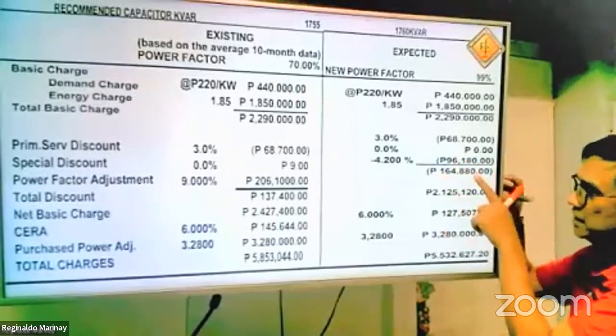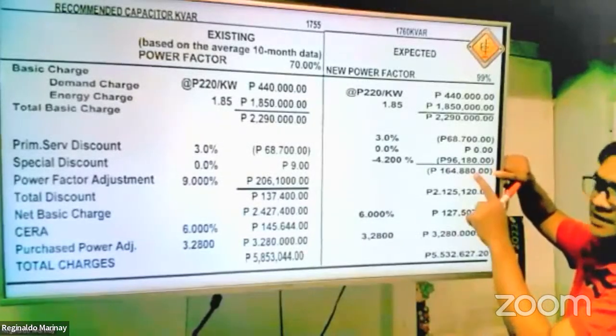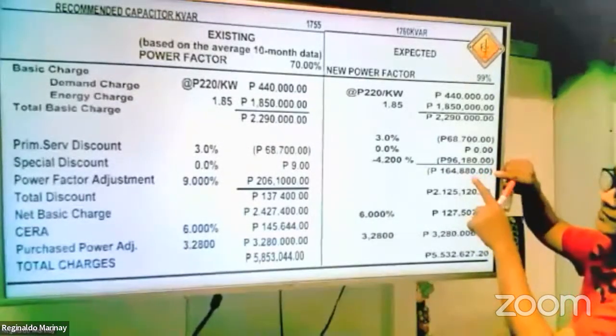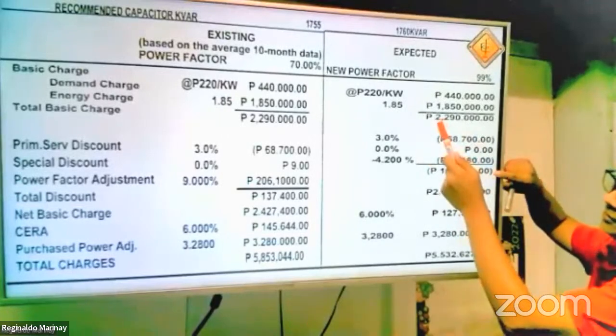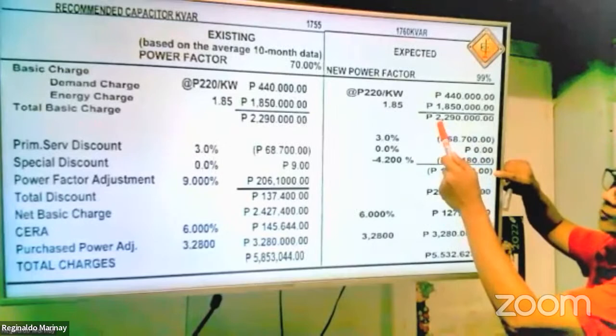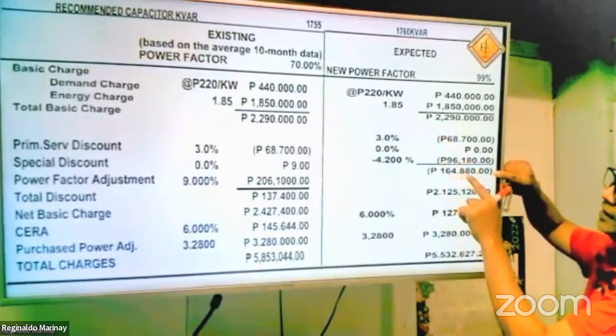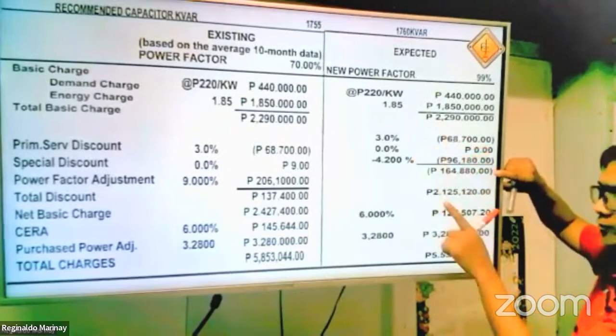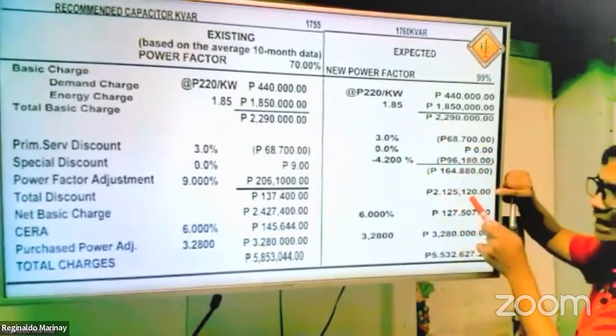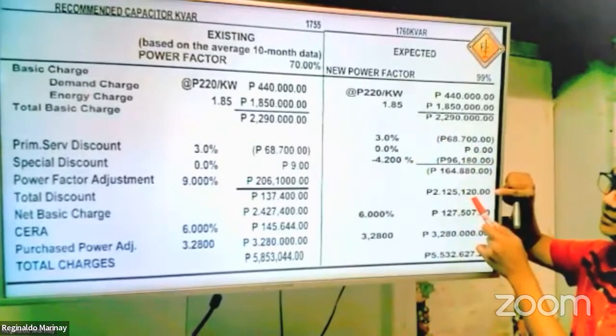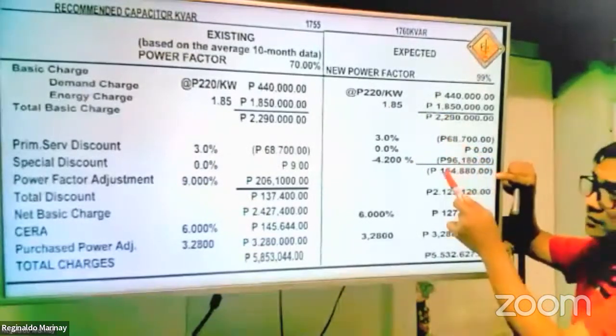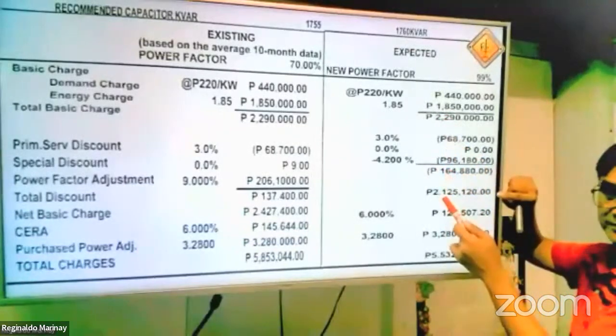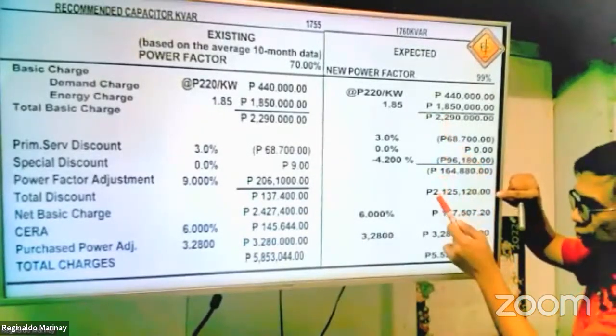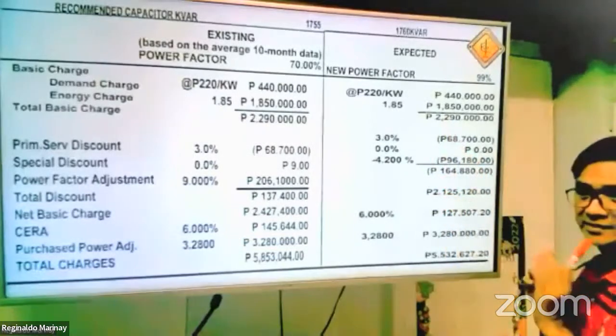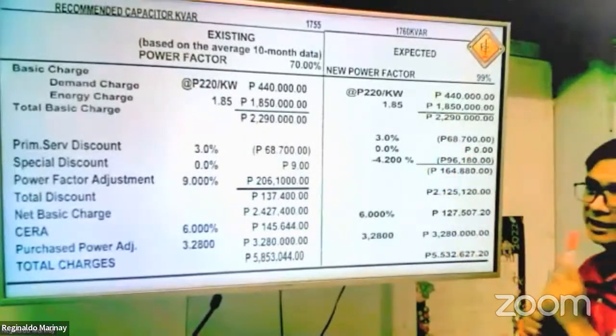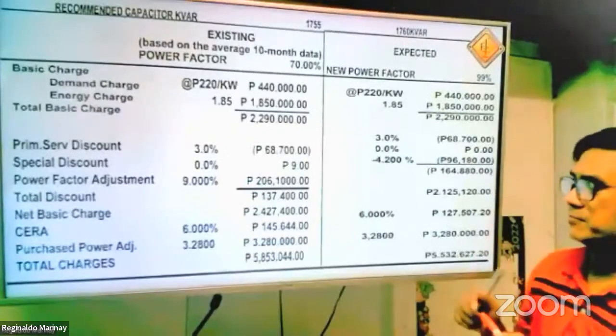164,880. Now, this is a discount, and that discount must be deducted from the total basic charge, the 2.29 million. If you subtract this 164,880 from 2.29 million, you will come up with 2,125,120 pesos. See? Because this is a discount, you already deduct from 2.29 here, from 2.29 million to 2.12 million. So it reduces, right? Because your power factor is 99%, higher than 85%.